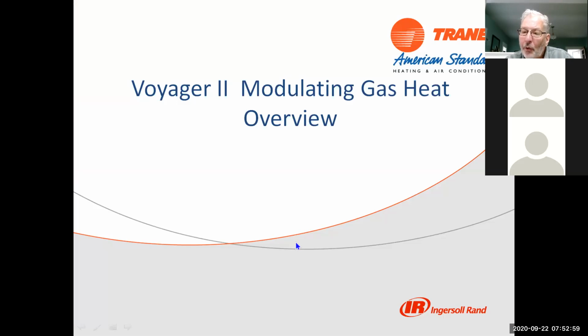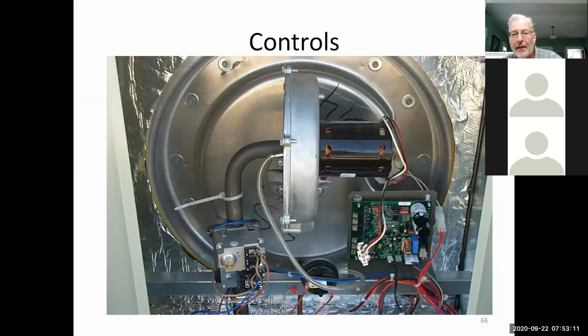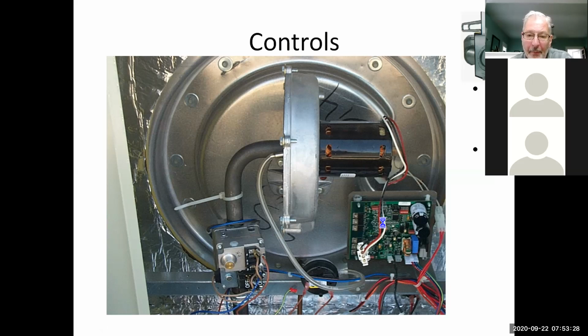All right, that was kind of a quick overview of the Voyager unit. We also have a Voyager modulating system out there, and I'm not going to spend a lot of time on it, but I want you to know that if you run into a modulating unit, it's going to look a little different. It'll have a pressure switch and a VFD board, and this is actually a 3-phase variable speed inducer motor or combustion motor. So the modulating is going to have a little different configuration. If you run into them, it's a little different animal.